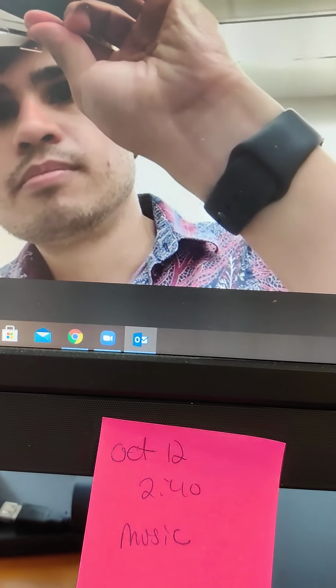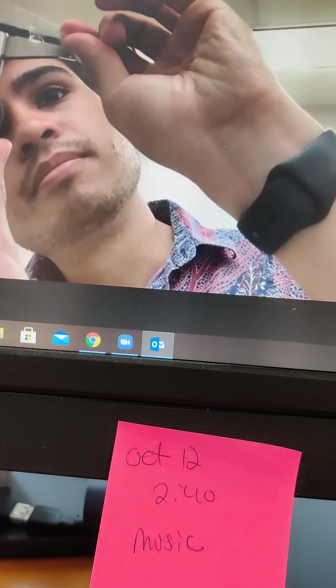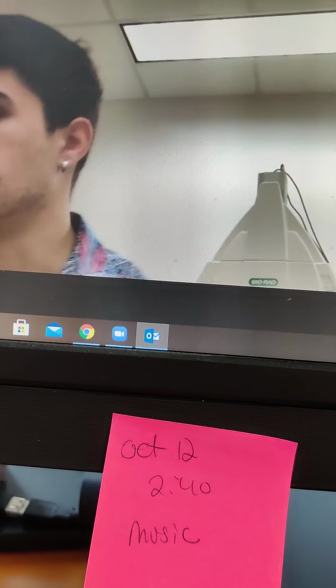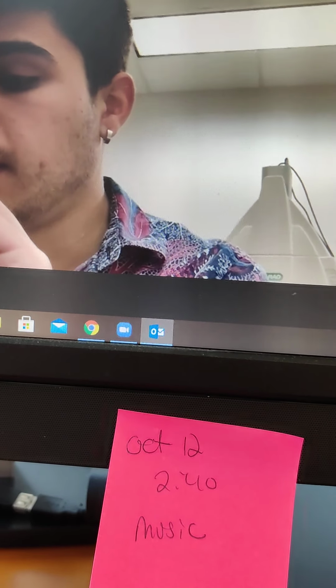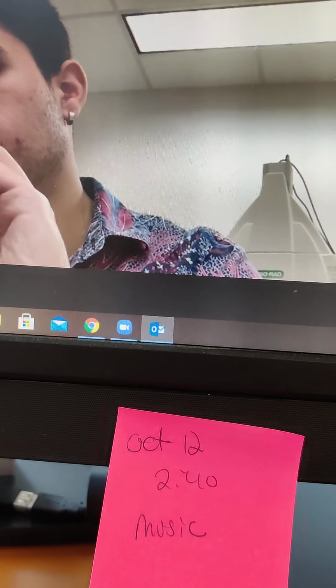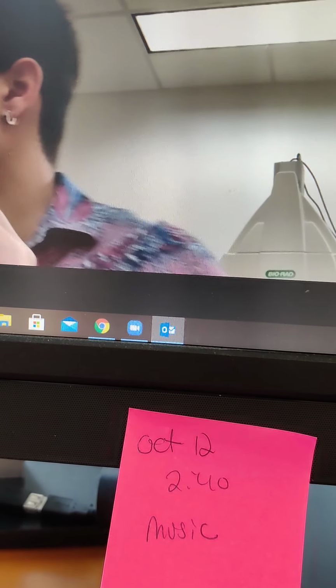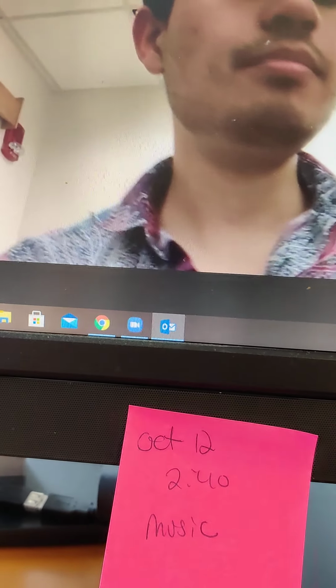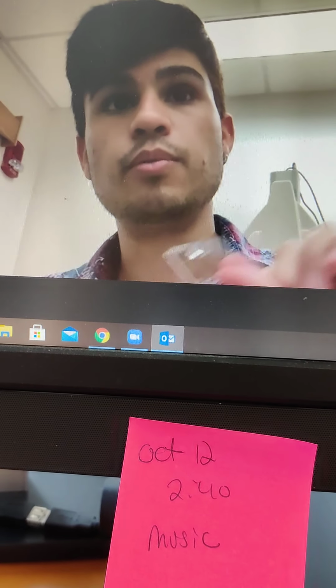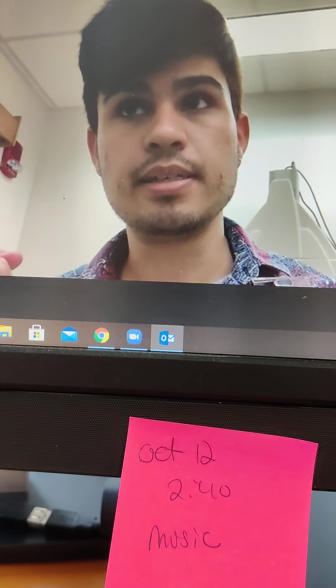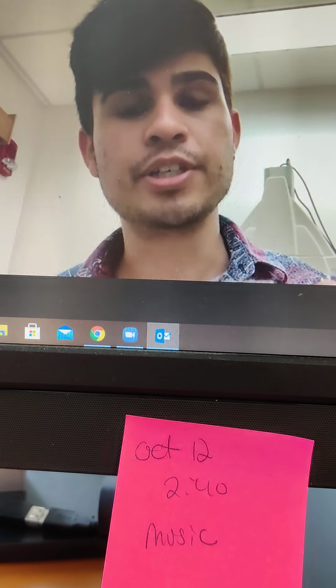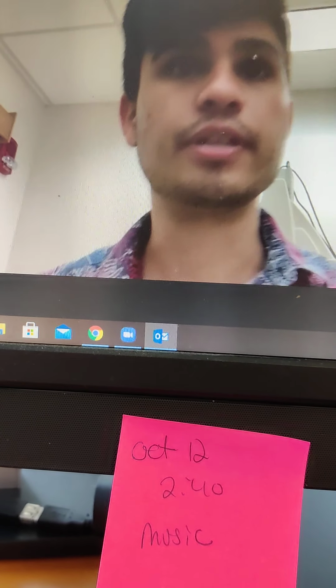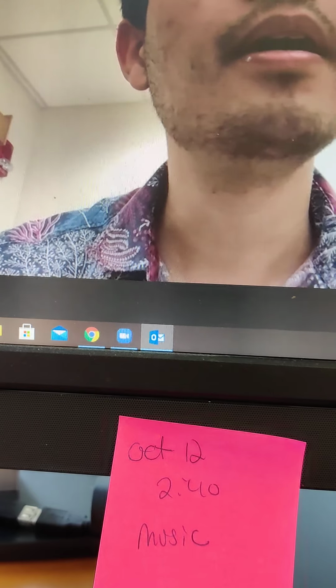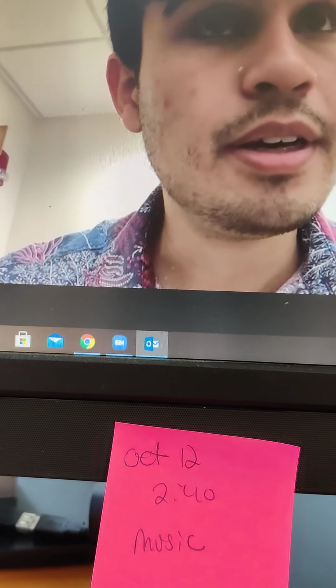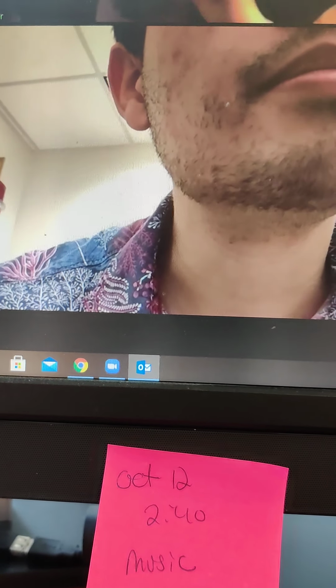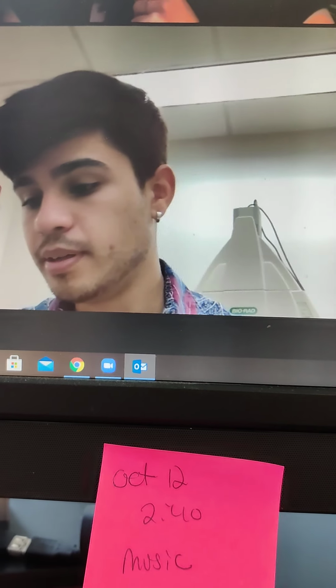Mm-hmm. 2.6. So this one's 2.6 millimeters with the slide, and then make sure you have a running measurement of the slide, 1.12. So 2.6 minus 1.12 is approximately 1.5. So in that case, 10% of that is 150 micrometers. So you want to make sure your load function doesn't go past 150 micrometers in depressing into the hydrogel. And it looks like this one that Mary has loaded up already for GMHA is 130 micrometers. So that works out.